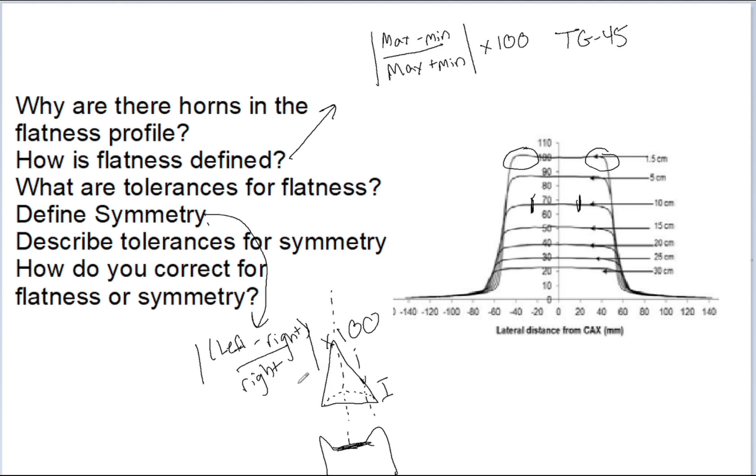The tolerance is very similar to the flatness. You want it to match your treatment planning system as well as the manufacturer's specifications. For symmetry, Varian specs are plus or minus 2%. And TG-40 says it could be plus or minus 3%.